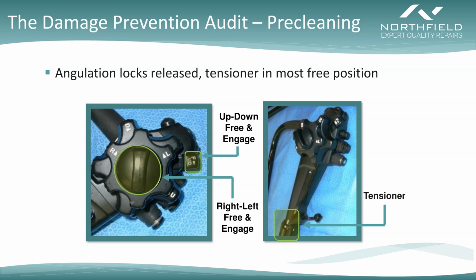Same kind of concept. If you're reprocessing your scope with those angulation locks engaged, that distal tip will still move, but you're stretching out your angulation wires in the process. So you're going to see much increased wear and tear on your angulation system if you are not putting those locks in the free position every single time as reprocessing is initiated.